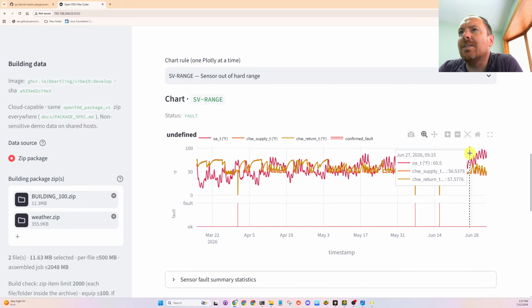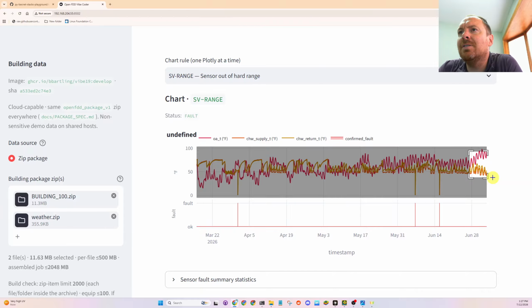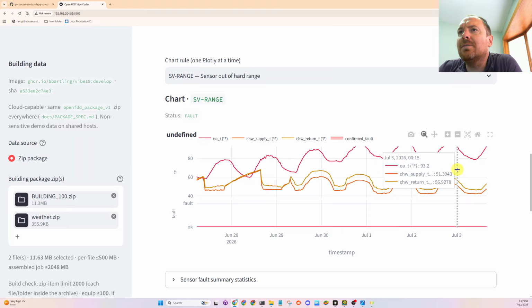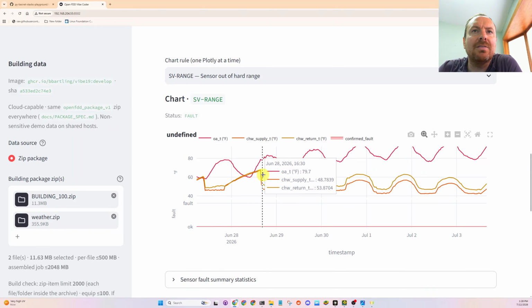And then if we get down in this information, down here, this would be like when the chiller is running during the day. So it does get like a 10-degree delta across it. This must be when the chiller doesn't run.